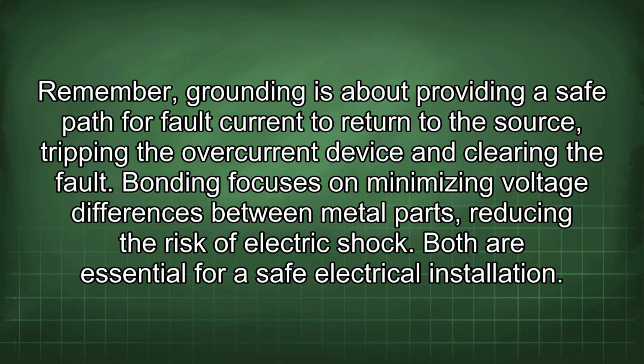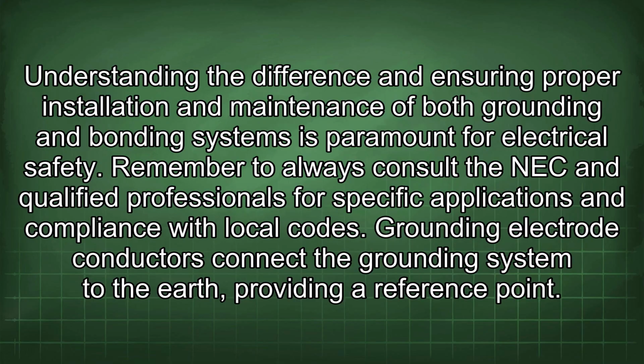Remember, grounding is about providing a safe path for fault current to return to the source, tripping the overcurrent device and clearing the fault. Bonding focuses on minimizing voltage differences between metal parts, reducing the risk of electric shock. Both are essential for a safe electrical installation. Understanding the difference and ensuring proper installation and maintenance of both grounding and bonding systems is paramount for electrical safety. Remember to always consult the NEC and qualified professionals for specific applications and compliance with local codes.